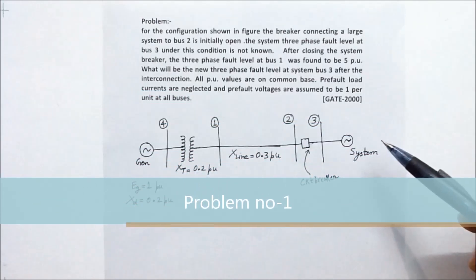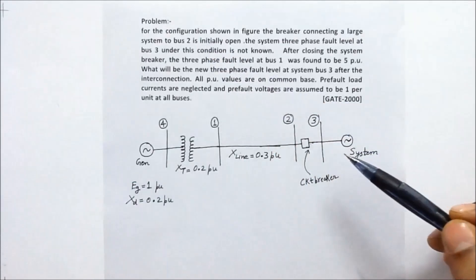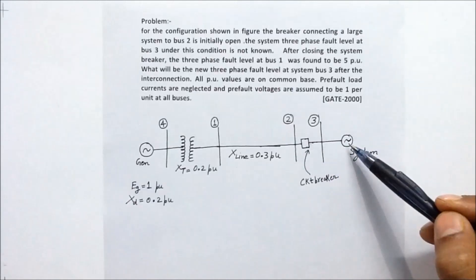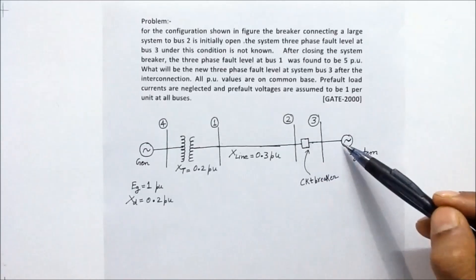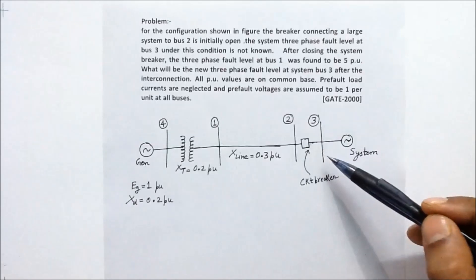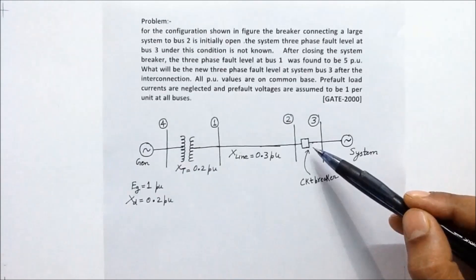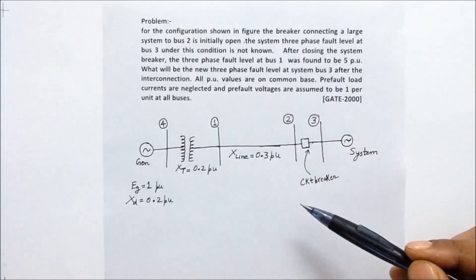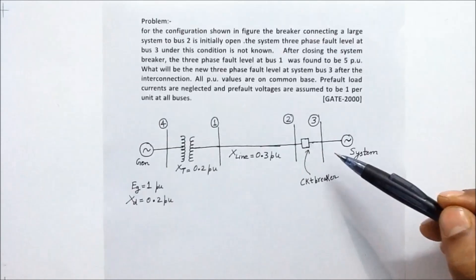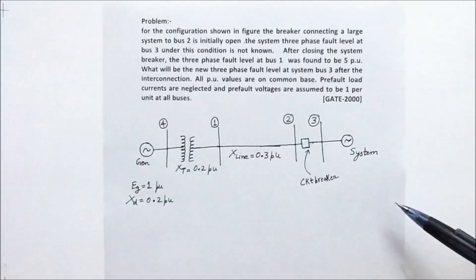I am going to solve this problem. Before solving, let me read it carefully. For the configuration shown in the figure, the breaker connecting a large system to bus 2 is initially open. The system 3-phase fault level at bus number 3 under this condition is not known. After closing the system breaker, the 3-phase fault level at bus number 1 was found to be 5 per unit. What will be the new 3-phase fault level at system bus 3 after the interconnection? All per unit values are on a common base, pre-fault load currents are neglected, and pre-fault voltages are assumed to be 1 per unit at all buses.